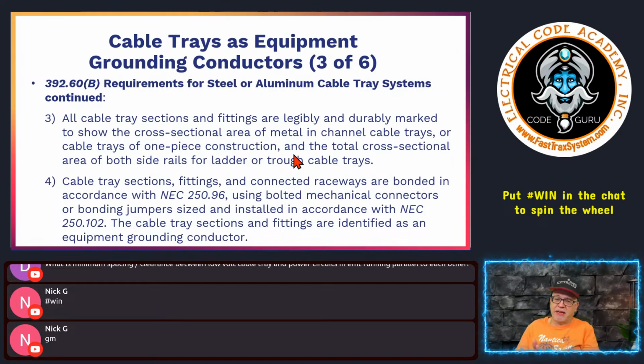That's pretty significant. If the cable tray itself can be used as an equipment ground, then it has to be legibly and durably marked. It has to have its cross-sectional area on there. Otherwise, how do you use Table 392.60(B)? You can't, okay? And you say, well, I'll measure it out. Well, no, the manufacturers have to provide you these markings, okay? If it's not there, reach out to your manufacturer. Don't just assume because it's metal, okay?